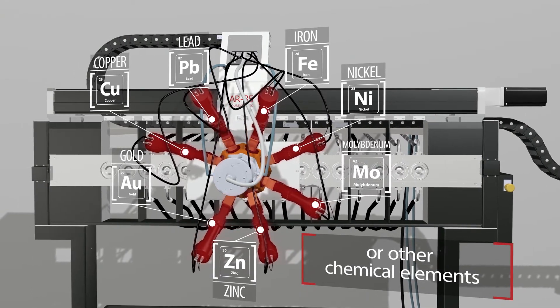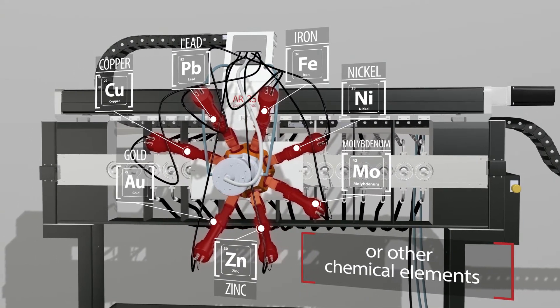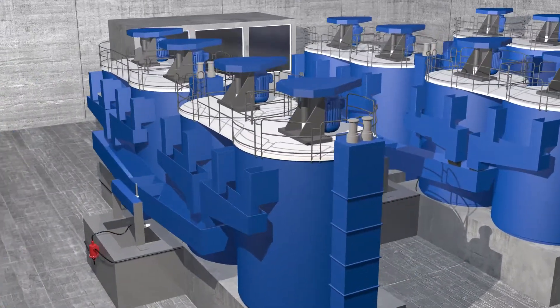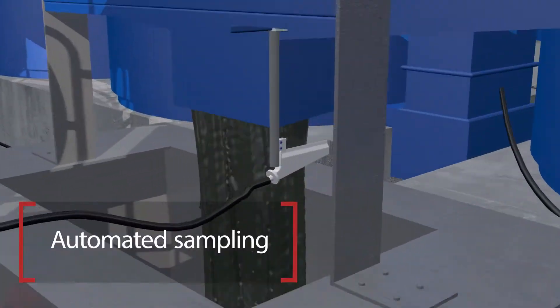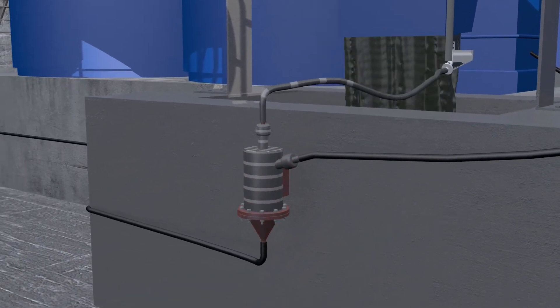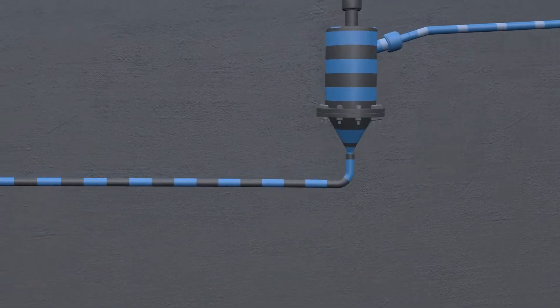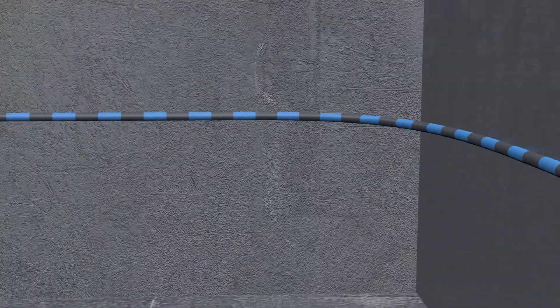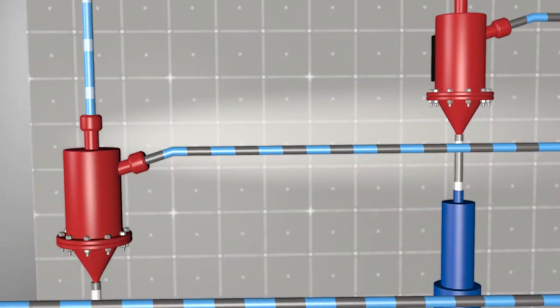Sampling and sample delivery are performed automatically without required labor. Samples from remote or low-lying sampling points can be delivered with compressed air or pumps. Dedicated sample feeders ensure uniform flow through the measuring cell of the analyzer, thus minimizing any measurement error.